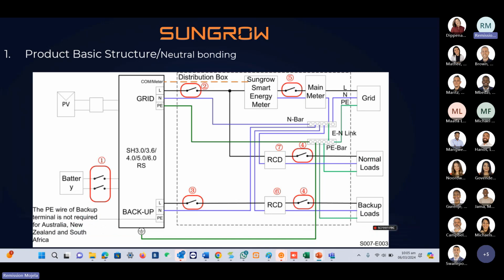And then this is the basic structure basically. We do have a neutral to neutral bonding. Basically, it's just the neutral commonization externally through the DB, or you can bond it if possible, but it's an external bonding. You don't need to use a relay. Basically, that's the structure of the system. This is also included in your installation manual. We just put it here so that we can highlight that if you do not have the neutral bonding, when your system changes over, a lot of the lights will flicker, or some of the loads might even switch off when it's time to change over from grid to backup.